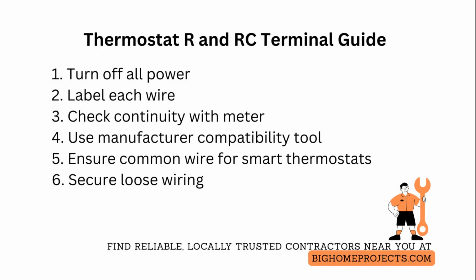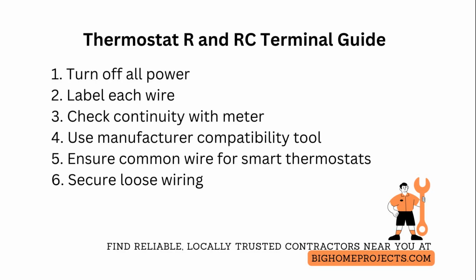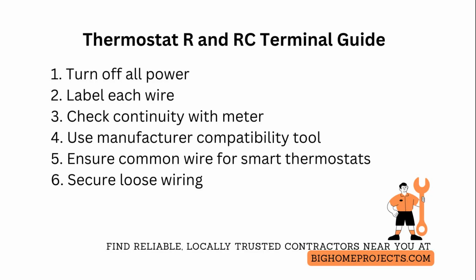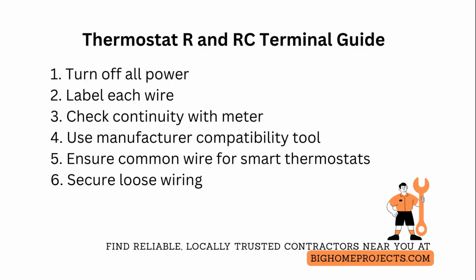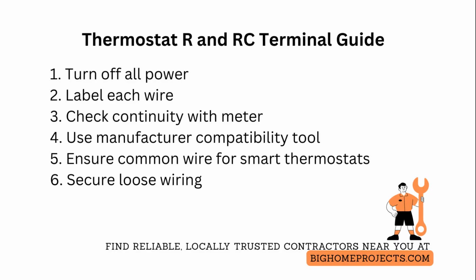For multi-stage systems or heat pump setups, the labeling changes. Look for O, B, and auxiliary terminals, W2, E. And in those cases, keep jumpers only as the equipment manual specifies. Finally, always secure loose thermostat wiring so it cannot short the control board. And if you are unsure, stop and call a licensed HVAC technician rather than guessing.